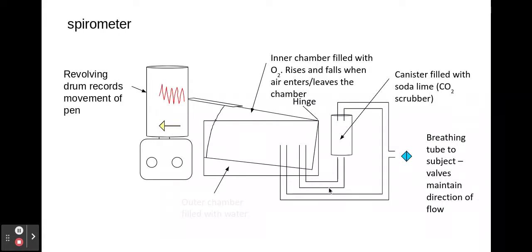Within the spirometer you'll have valves which aren't shown on this diagram. They control the flow of the air in one direction in and another direction out, but it needs to make sure that the air passes over the soda lime.